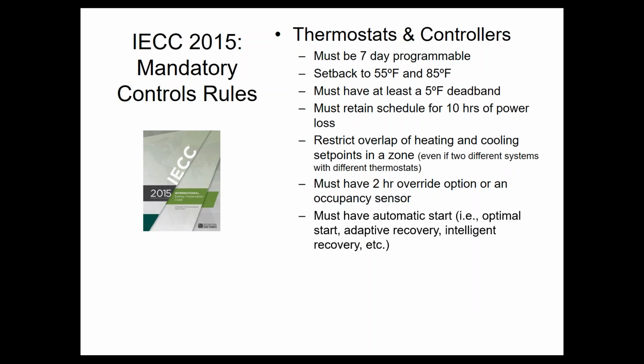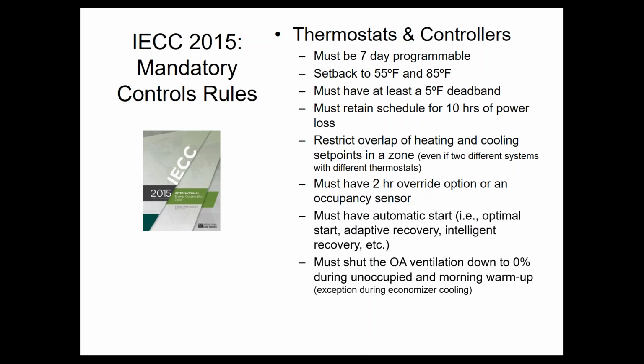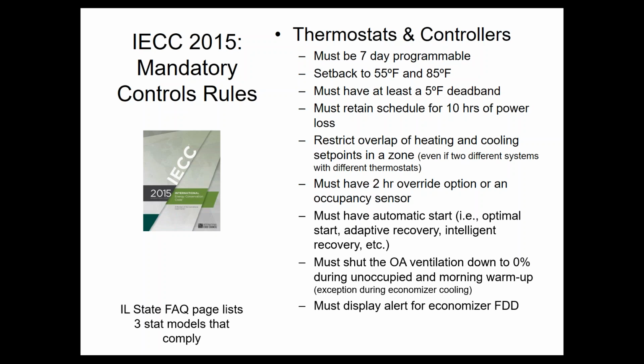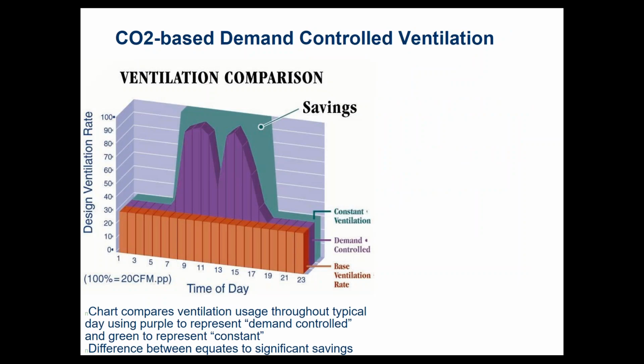You have to have adaptive recovery or optimal start on there. That's where the thermostat starts before the scheduled time in order to get to the exact set points at the time that you asked for. That's required of all the thermostats and controls. You got to have the ventilation interlock like I talked about before. That's required. You got to have the ability to display the FDD alarm. That's a requirement, right? So there's quite a few things going on there in terms of controls. Whether you have thermostats or whether you have DDC controls, you have to do all of these.